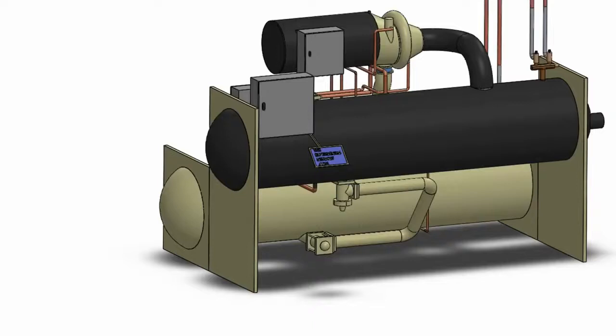But first, what does an expansion valve do? Well, the expansion valve controls how much refrigerant flows between the condenser and the evaporator. The valve responds to the suction line superheat which is entering the compressor. This is the suction line here going into the compressor, and it will vary the amount of refrigerant flowing in to suit the change in the cooling load.